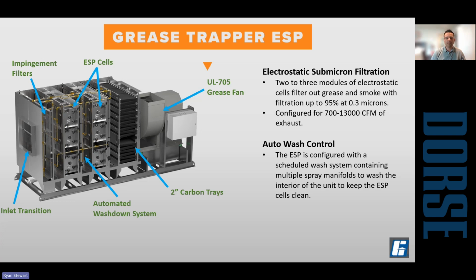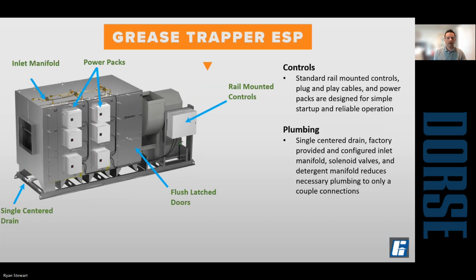So it's using electrostatic cells. They're capable of removing up to 95% of the grease down to 0.3 microns. So that's going to be your smoke particulate. And then they're configured with a wash system. So once the cells collect that grease at the end of the day, it'll go through a wash system and rinse it off those collection grids. So this is what it looks like assembled.